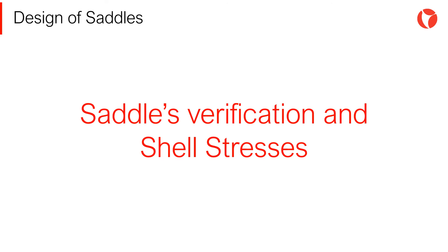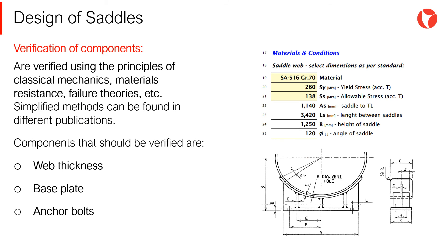Once the configuration and dimensions of these elements have been determined, it is necessary to verify the stress levels induced by the design loads. These elements are verified using the principles of classical mechanics, material resistance, failure theories, etc. Simplified methods can be found in different publications, adapted to the configuration of this equipment. Components that should be verified are: the web thickness, the base plate, and the anchor bolts.